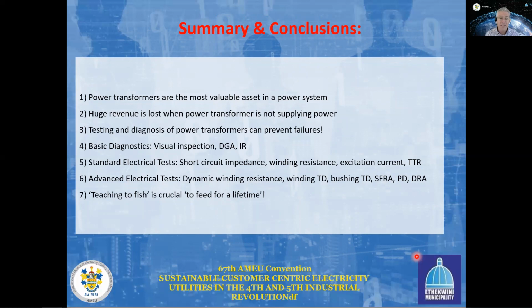There are standard electrical tests available, such as short circuit impedance, winding resistance or static winding resistance measurement, excitation current measurement, and transformer turns ratio measurements, which can be done on a regular basis. It should take you no longer than an hour to conduct on a typical distribution transformer. And then there are the advanced electrical tests available, such as the dynamic winding resistance measurement for the on-load tap changer, the winding dissipation, the winding tan delta, the bushing tan delta, the sweep frequency response analysis, the partial discharge measurements, as well as the dielectric response analysis on a transformer, that can be used as advanced diagnosis methods to diagnose your transformer.